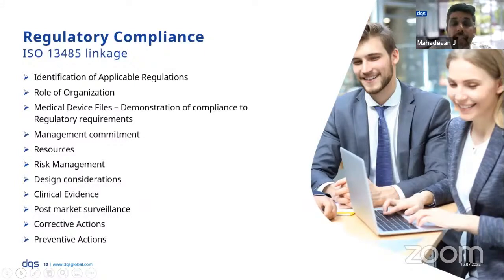Post-market surveillance activities are extremely important from any regulation perspective, where you need to monitor the performance of your device, including complaints investigation and reporting to any regulatory authorities in terms of adverse events and whatnot. The requirements are all given in various regulations. So ISO 13485, if you look into clause 8, 8.2.1 to 8.3.4, most of the things are related to monitoring your device, post-market monitoring of your device and subsequent actions, including the reporting to the regulatory authorities.